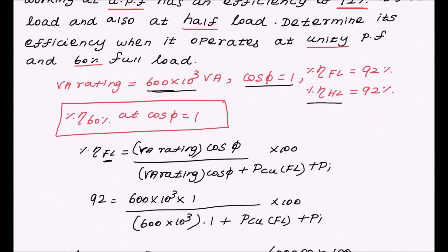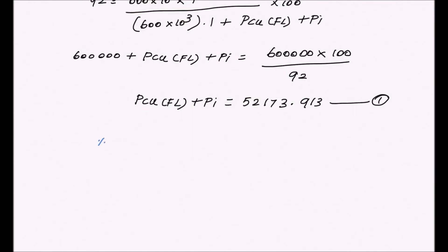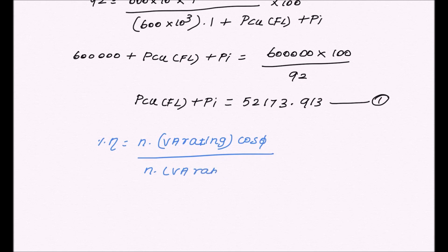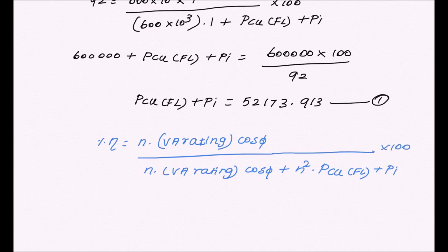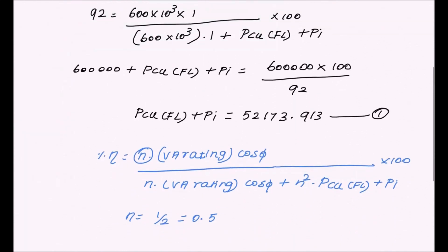The efficiency at half load is given as 92%. For fractional load, the percentage efficiency formula is: (N × VA rating × cos φ) divided by (N × VA rating × cos φ + N² × full load copper loss + iron loss) × 100, where N is the fraction of the load. For half load, N = 0.5. At half load, efficiency is 92%, power factor is 1, and VA rating is 600 × 10³.